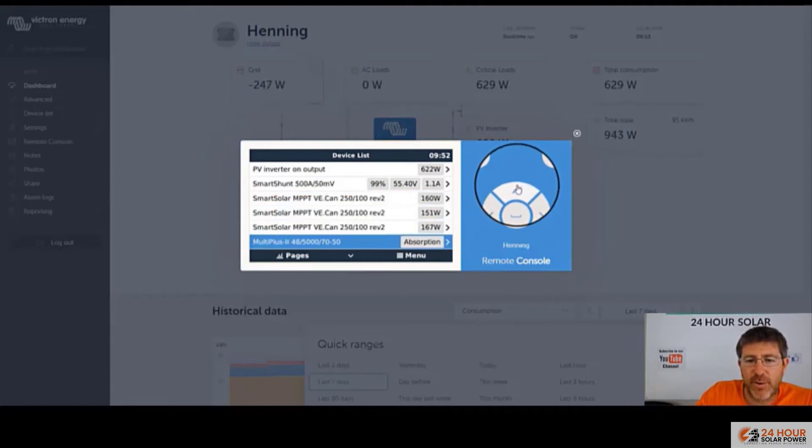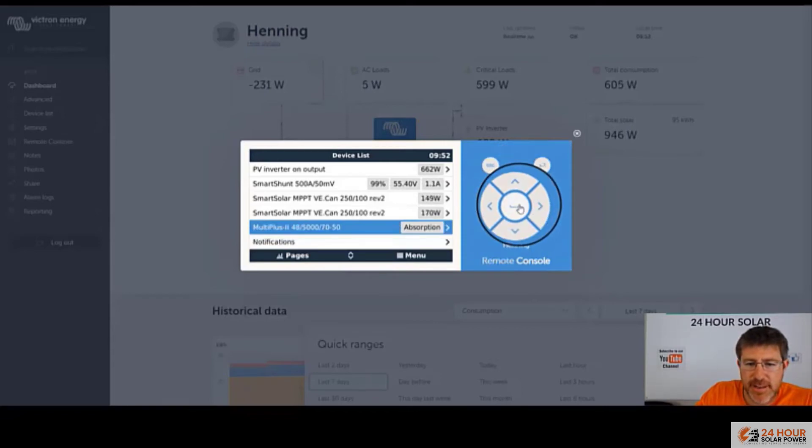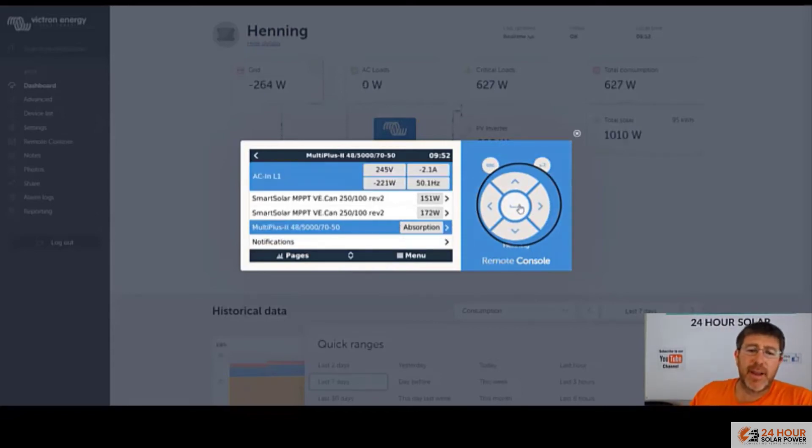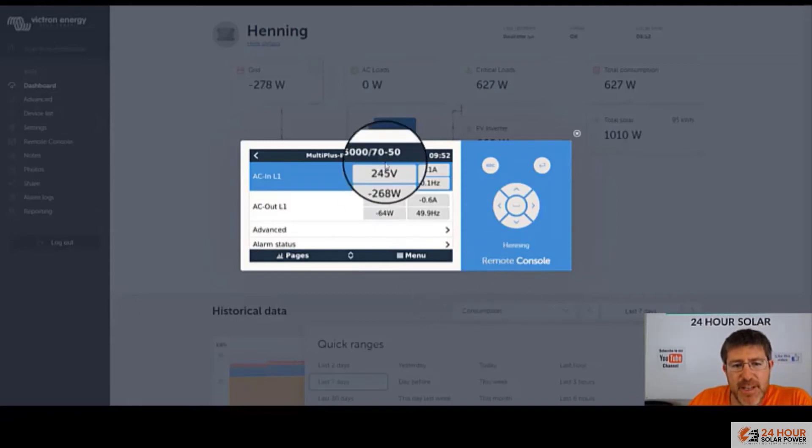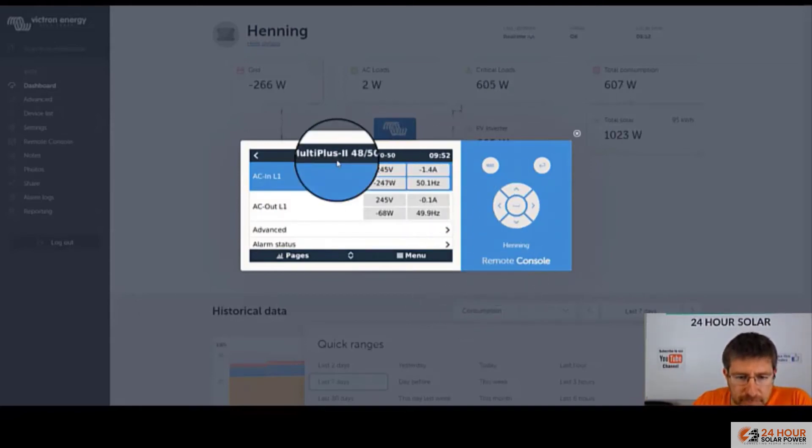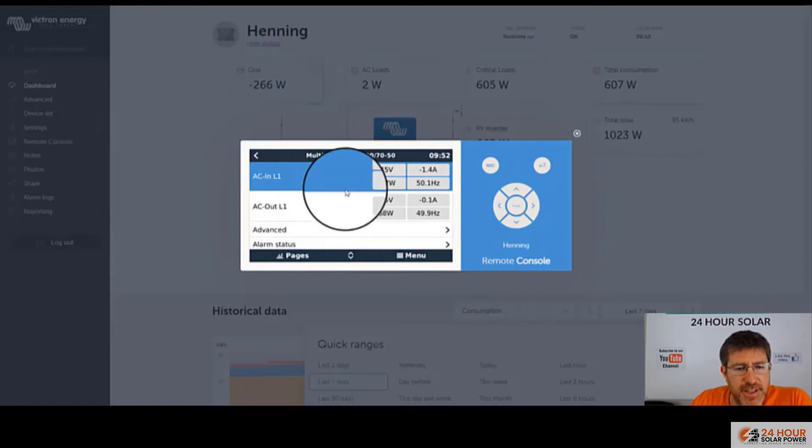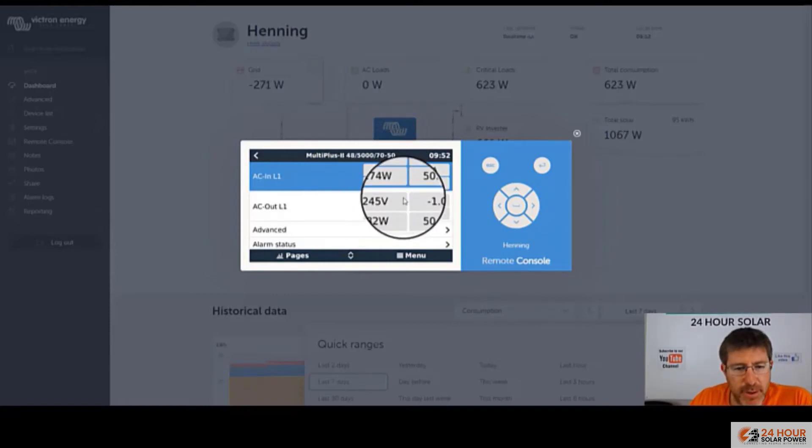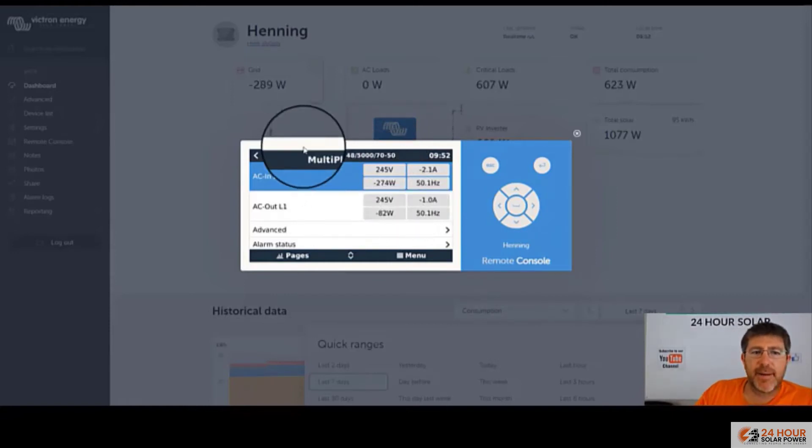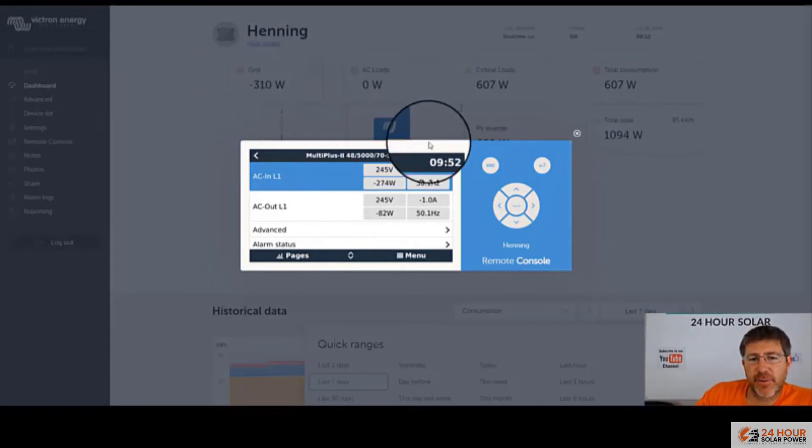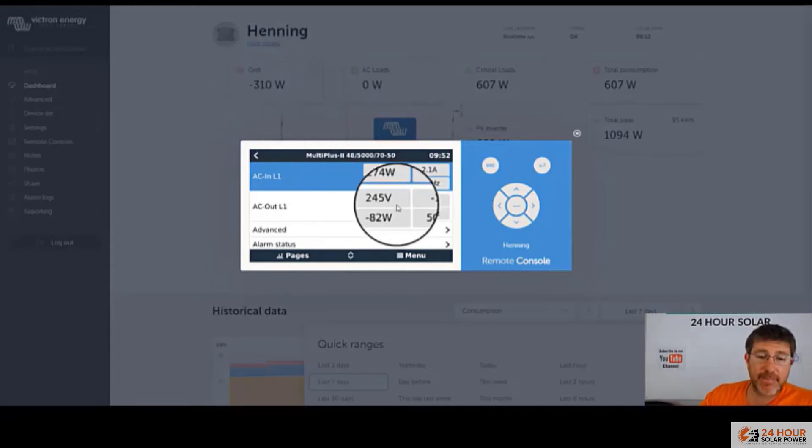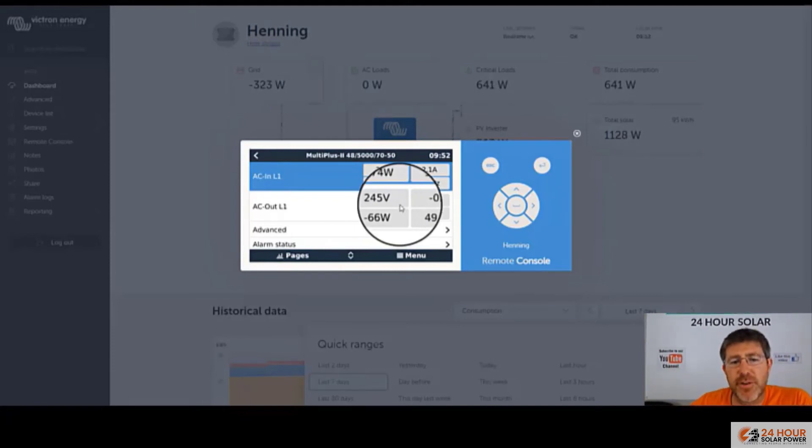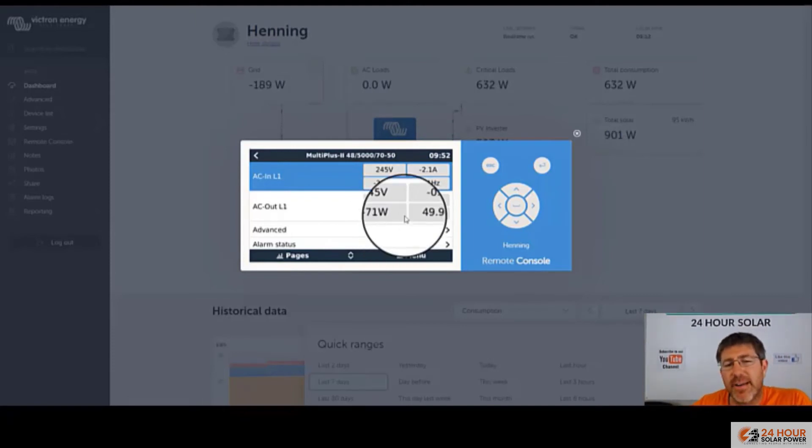We'll have a quick look in here of some cool features with this multi-plus. Things I like to look at in here with the multi-plus. Here in Australia, one of the biggest problems is we have high grid voltages when we feed too much back to the grid. So this system here is 245 volts as a grid voltage, which is pretty good. As you'll see, it's actually not feeding that much back to the grid at the moment.